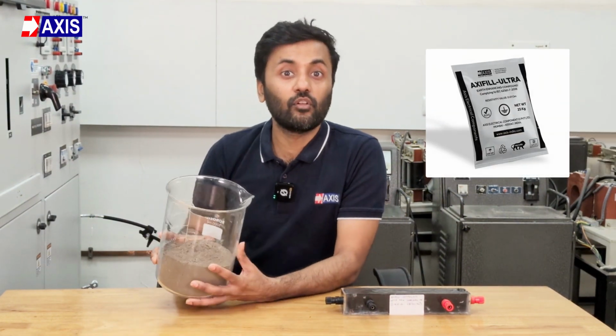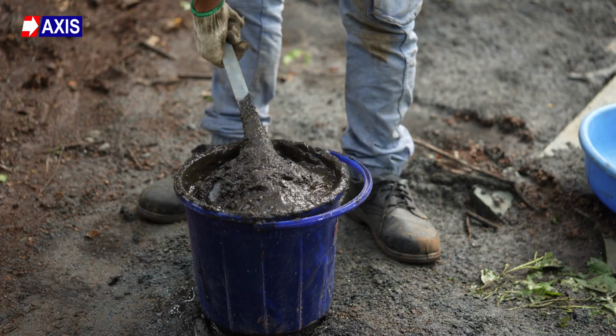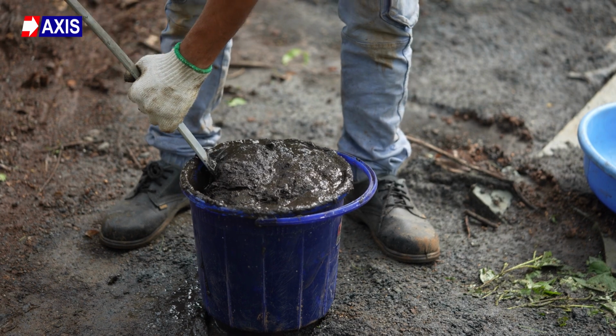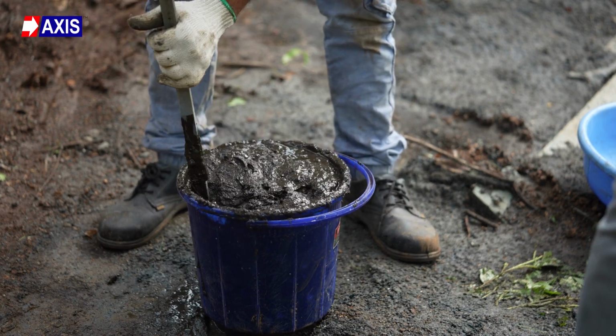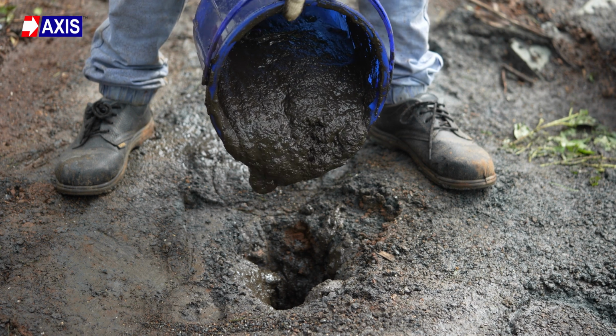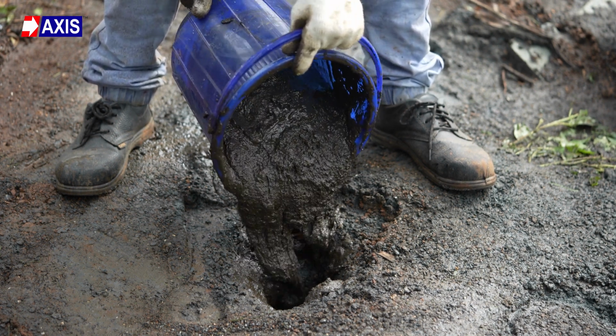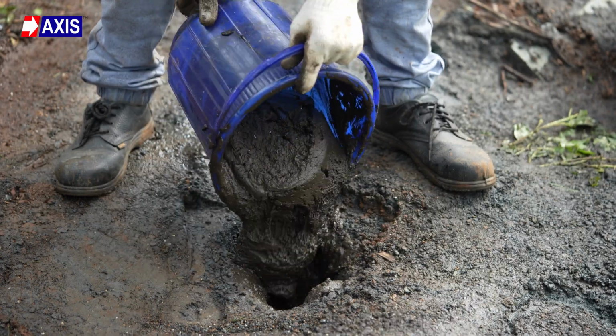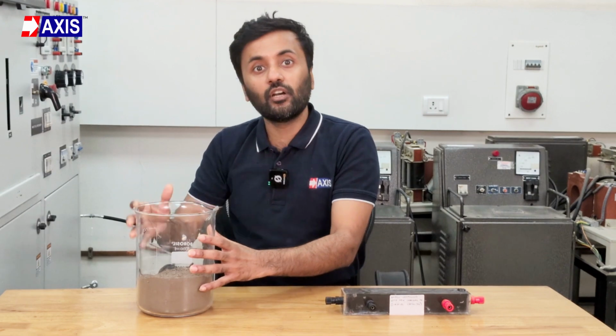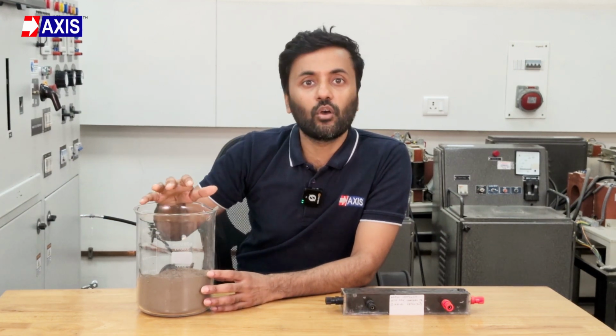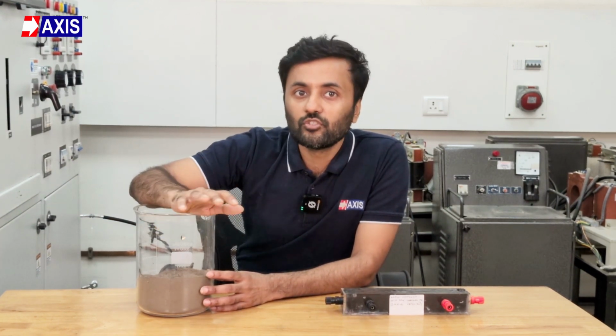Axifill Ultra is designed to solve these problems. When Axifill surrounds the electrode, the moisture will still mix with the compound and form an electrolyte solution. But because it has a pH level controller, it will maintain a neutral environment around the electrode. So even if the surrounding soil is uneven, the compound will create a safe zone around your earth rod. As a result, the electrode gets better contact with the soil, low electrical resistance, and better protection from corrosion. It obviously also supports conductivity through moisture and conductive fillers without attacking the electrode surface. The copper patina or zinc coating on galvanized iron remains stable, so the metal below does not get exposed. This improves the long-term life of your earthing system.